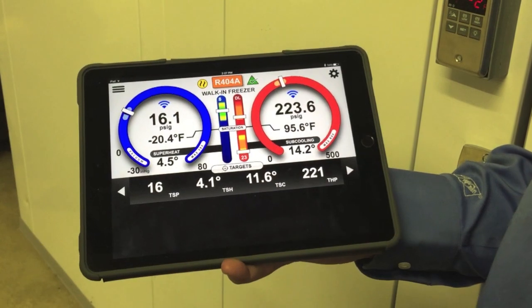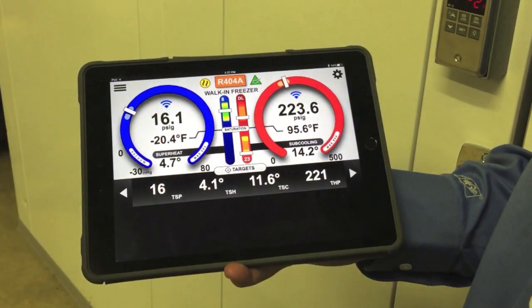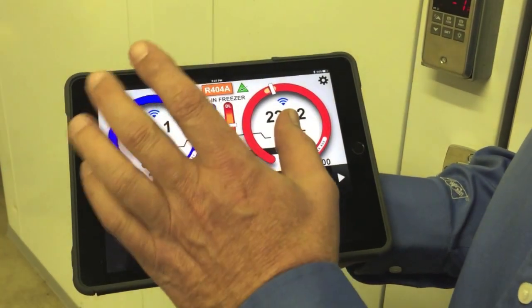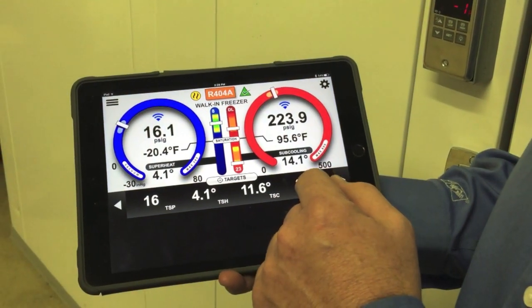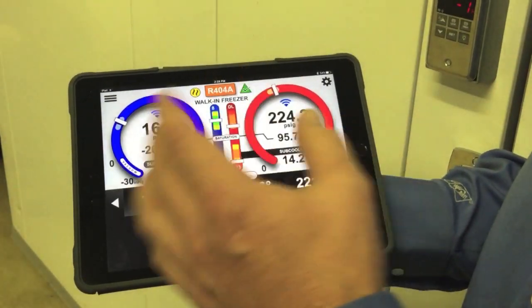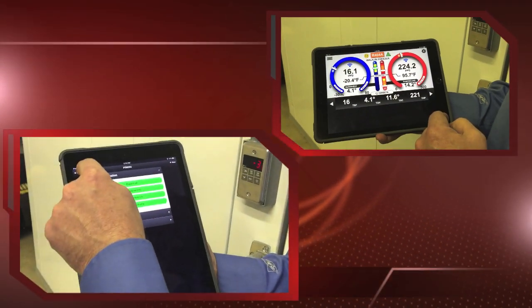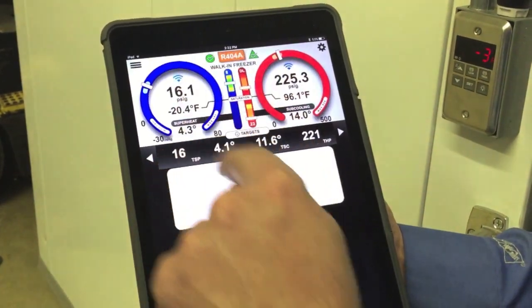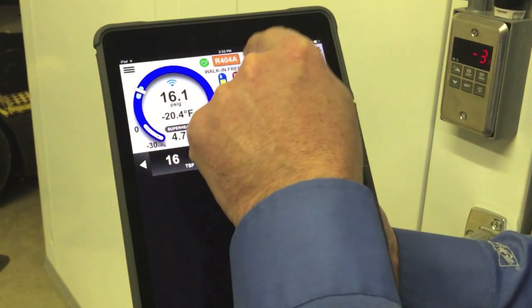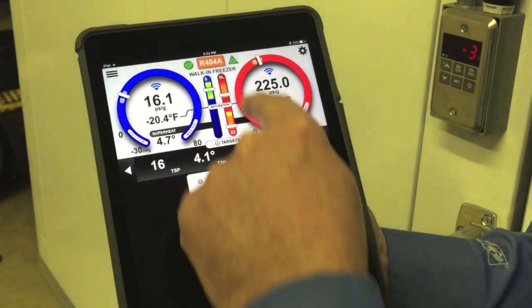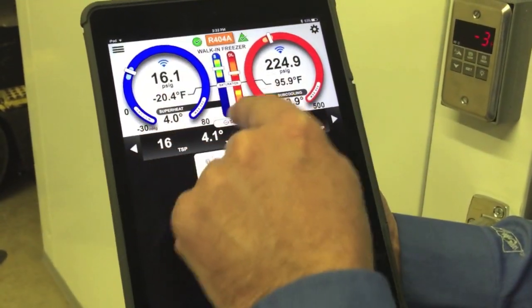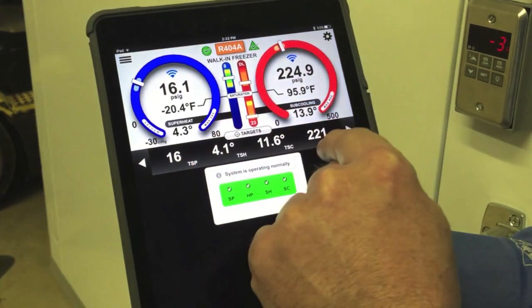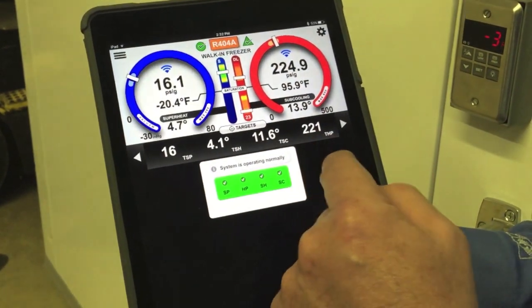And that's the beauty of the I-Manifold application — we're showing exactly where that pressure should be, our target. Right now our target is 16, and we're at about 16.1. The box is probably going to be very close to satisfying here pretty quick, but it's allowing us very quickly to see if things are falling into the right range. Now you can see the system has stabilized — that's a stable temperature split and stable liquid line temp. Everything is operating normally because everything is falling within the design parameters for the low side, high side, superheat, subcooling, and the discharge line temperature is well below the allowable range.